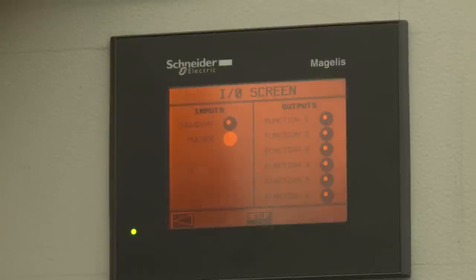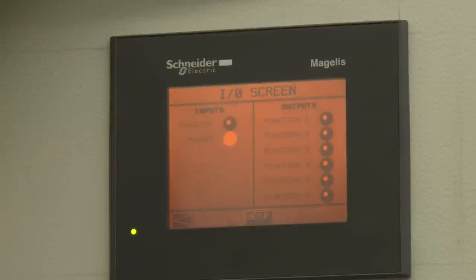If we do detect a truck, these are our six functions. We can stay here and watch to make sure each one of them is coming on and programmed properly. We could be looking at a pump that's running, and then when the truck bed arrives, if this light comes on, that pump goes off. It's easy to troubleshoot and see what's going on.